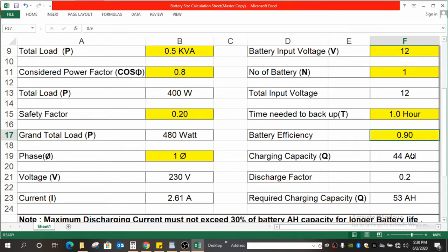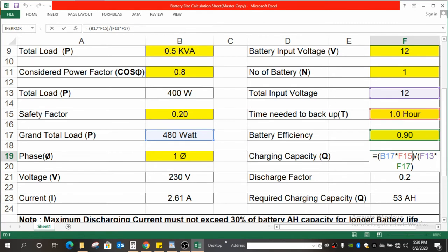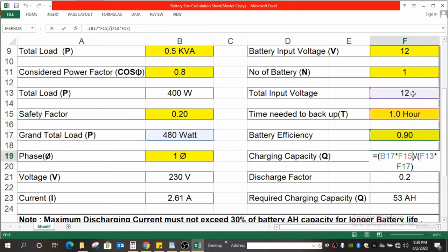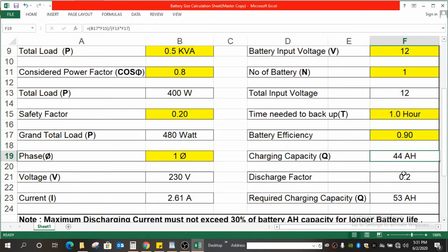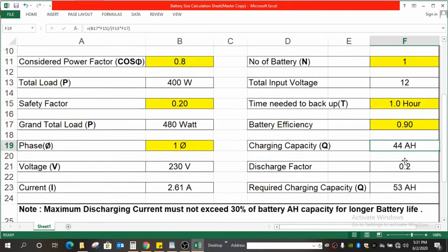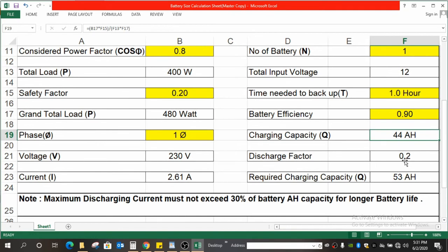So we got 44 Ah as per actual requirement. The formula over here is B17, that is the power in watts, multiplied by F15, that is the time needed to backup, divided by F13, that is the total input voltage, multiplied by F17. This is the formula entered over here.